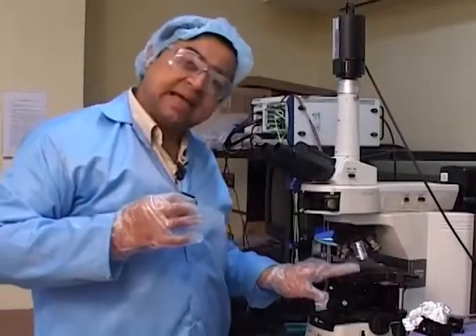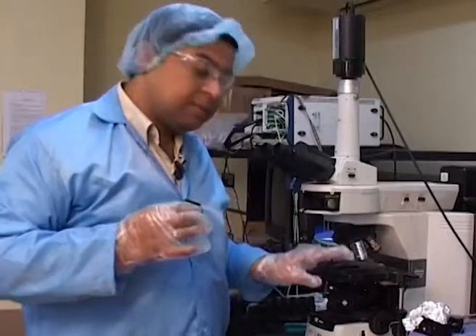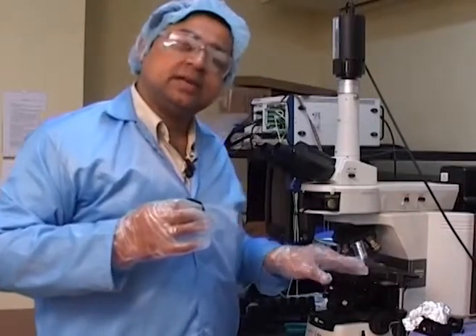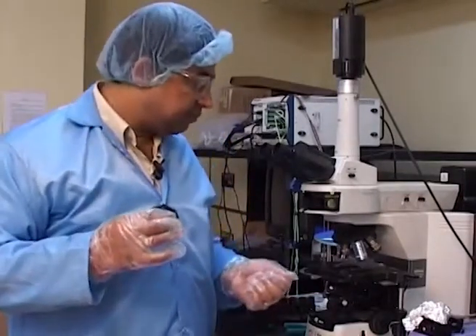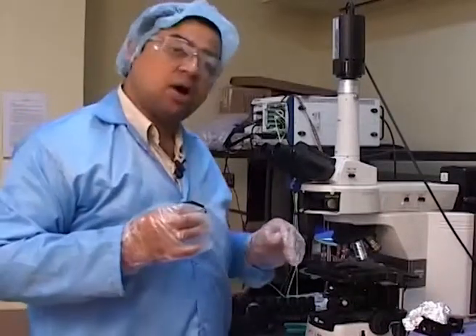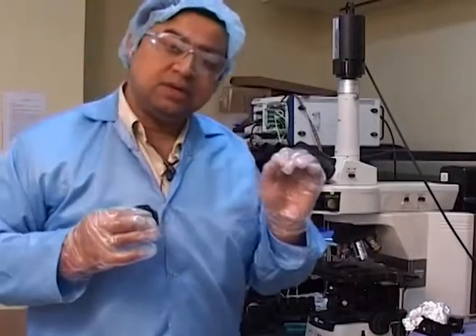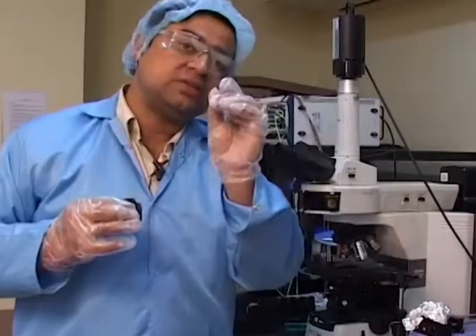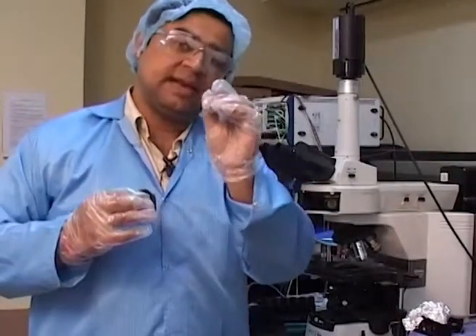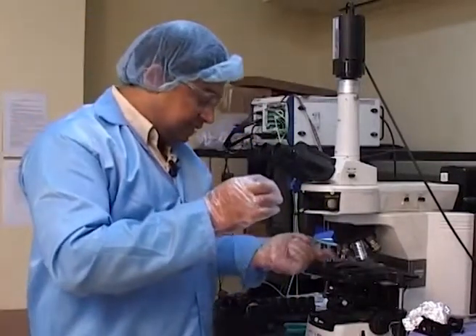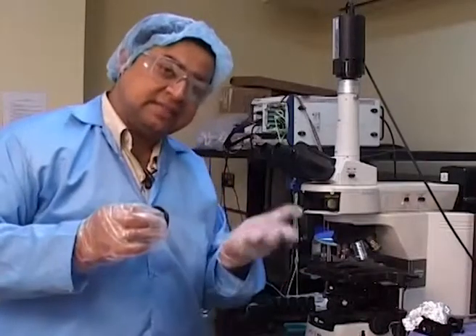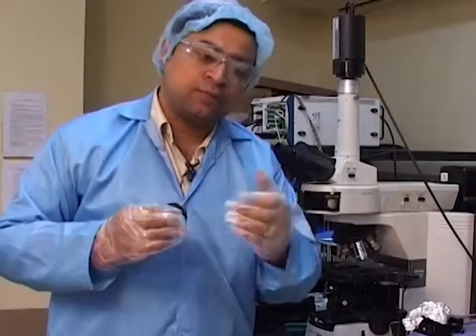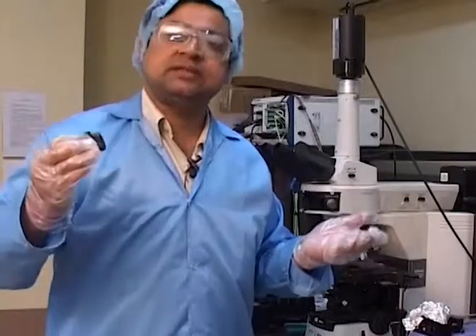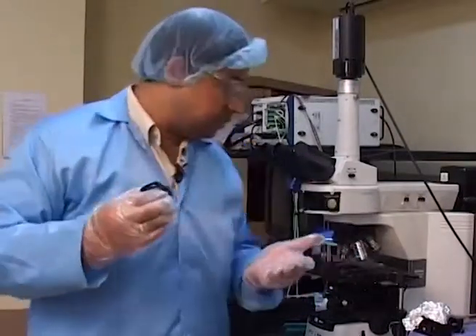This right here is the sample stage. It is an XYZ precisely moving stage which is capable of positioning the sample with respect to the objective. And we can maneuver over the sample and see the zone which we want to focus on and image. So essentially, when the light goes and strikes the sample surface and there is a fluorophore, there is an emanation of a certain frequency, which is the emission frequency of the particular fluorophore.